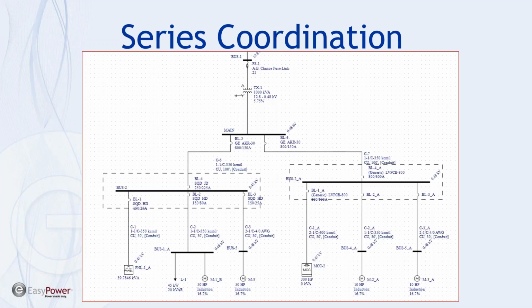The topic of series coordination we actually cover in multiple webinars, and the basic process is the same in any case. When a fault occurs in my system, I want to isolate it with the protective device closest to the area of the fault and thereby prevent the rest of the system from being pulled down due to that single fault. That requires that we schedule the trip timing of each of the protective devices in a serial fashion and slow down the ones above the bus that needs to trip first.